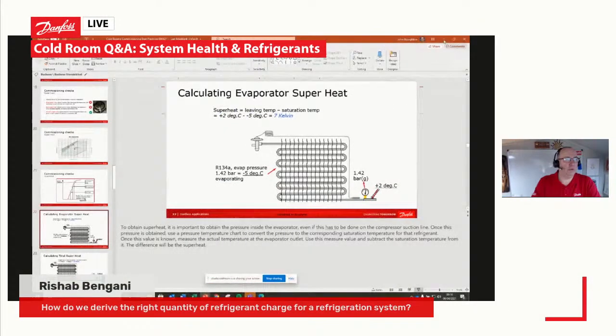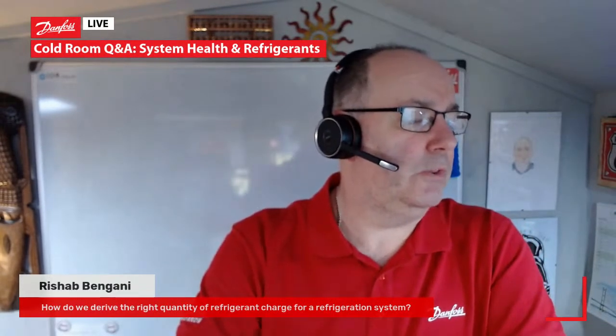Basically, and this goes back to the way I was taught when I was much younger, when I was on the tools, you charge a system to a full sight glass, which is, I would say, still the best way to make sure that you are there or thereabouts. But then you also need to make sure your suction pressure, your suction temperature and your discharge pressure are where they should be. Now, there is a very good tool that we have within Danfoss, and I'll just share my screen in a moment and show you, but I just need to load something up. So I'll just stop sharing my screen a second, and I'll load up Danfoss Coolselector software, which basically gives you a good indication of the pressures and temperatures that you should see around a system. So let's load that up on the other screen a second, and I'll show you what that would look like.